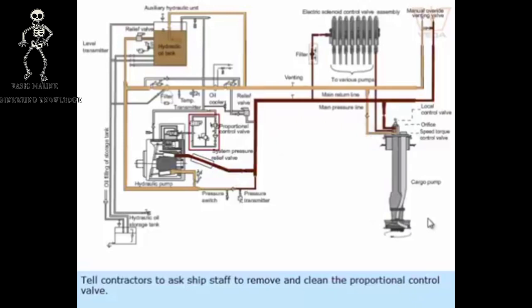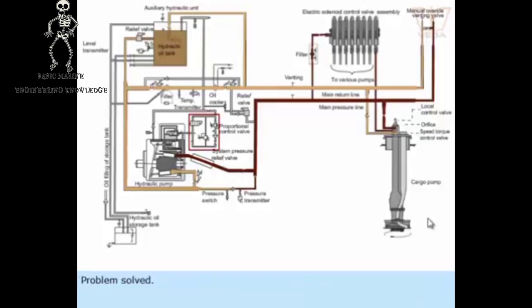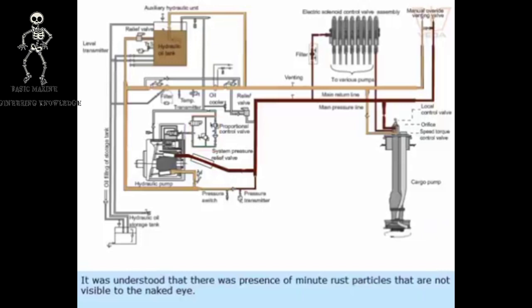Tell contractors to ask ship staff to remove and clean the proportional control valve. Problem solved. It was understood that there was presence of minute rust particles that are not visible to the naked eye.